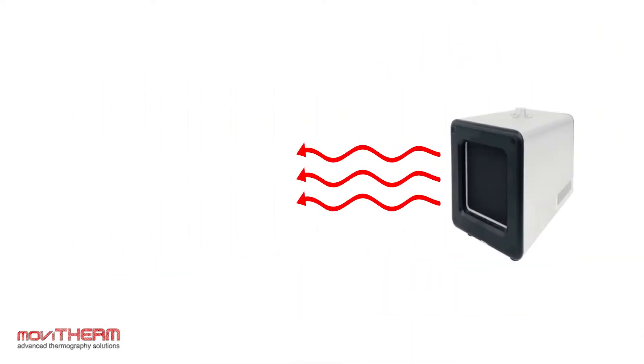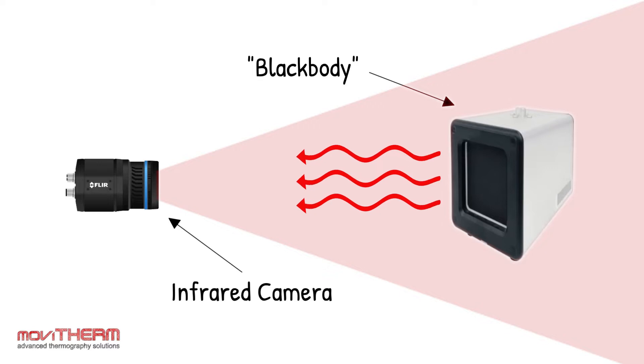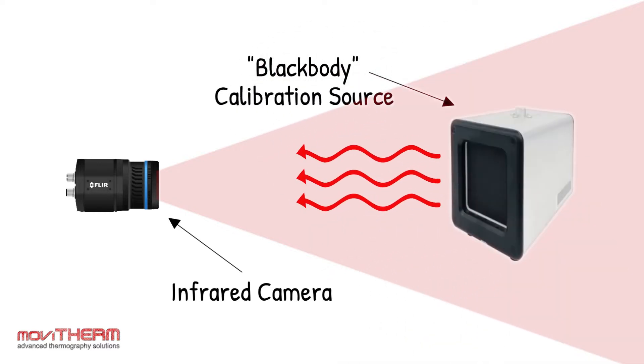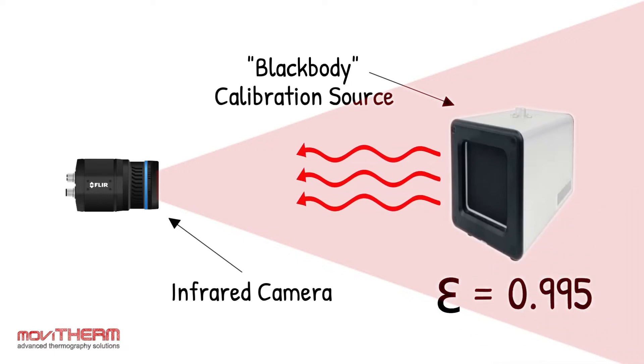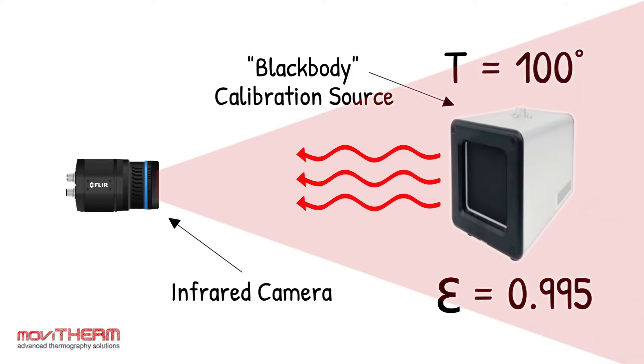Sources used to calibrate infrared thermometers and infrared cameras are sometimes called blackbodies. These calibration sources have a black radiating surface of high emissivity up to 0.995 and have integrated temperature control electronics. These blackbody calibration sources are programmed to emit infrared radiation at a specified temperature.